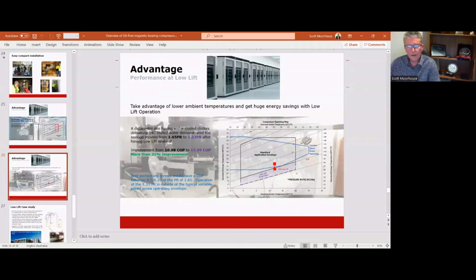Also, we can run at very low pressure ratios. So we can take advantage of the very low temperatures at night, where other compressors rely on a pressure ratio for their oil management, but we can reduce our pressure ratios extremely low and take advantage of the more efficient area where we run. When we run them extremely low, we do need to add a small refrigerant pump to boost the motor cooling and the inverter cooling.